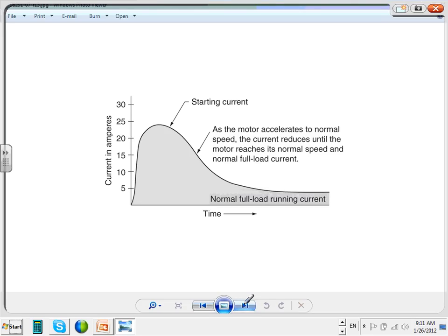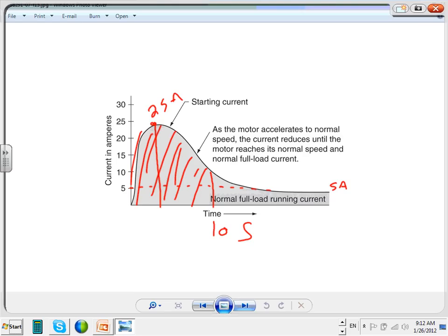When we have any motor, guys, you have the starting current for 10 seconds. 10 seconds, not infinity. You can have a current of almost all motors, continuous amp 25. So in this case, this motor is rated for 5 amps. When you start that baby, it's sucking out of the system 5 times 5, 25 amps, only for 10 seconds. This is what they call the starting current of a motor, guys. And that's why we size the fuses higher, the circuit breaker higher, so we can handle the starting point.